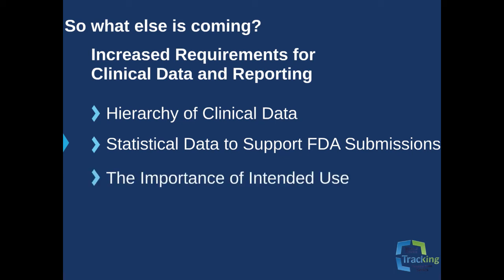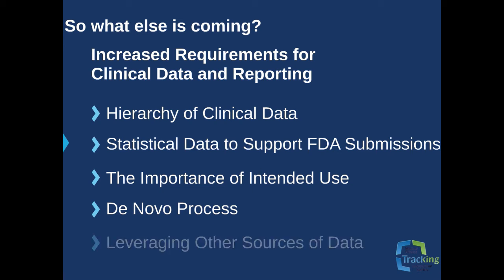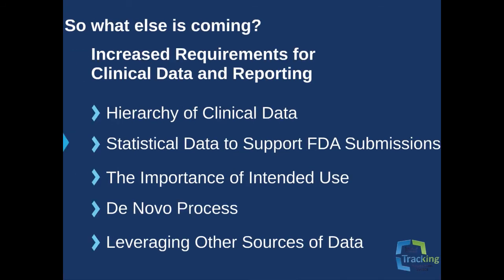The importance of intended use, statements made in the labeling regarding how the product is intended to be used by the healthcare professional. De novo process, sponsors submit de novo applications providing information to demonstrate that the product presents only a low to moderate risk to public health, even though the application does not meet all the requirements of a 510(k). Leveraging other sources of data. Companies can leverage clinical experience from outside the United States in lieu of a pilot study.